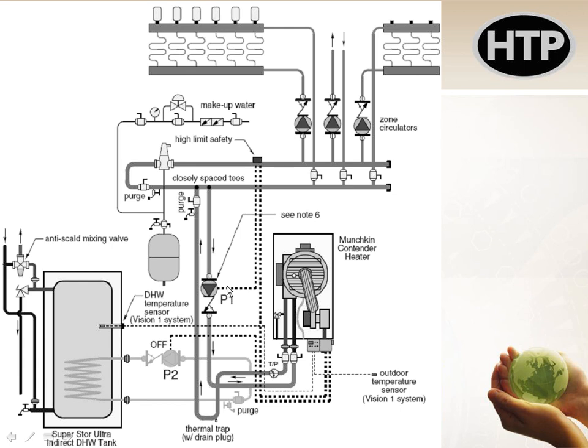If I have heating systems in the building that are radiant floor heating or other large mass heating, like cast iron radiators and things like that, if I stop heating those for 10 minutes and pull over and do the domestic water, no one's going to even notice. It's not going to affect the room temperature at all. So you can do that. You can use one boiler to do two jobs.